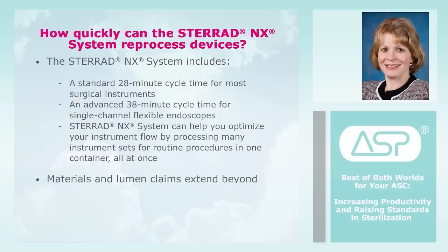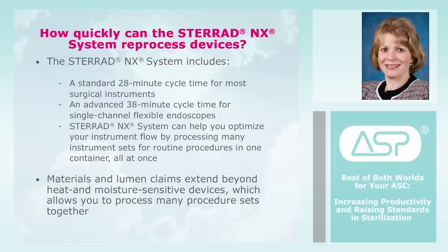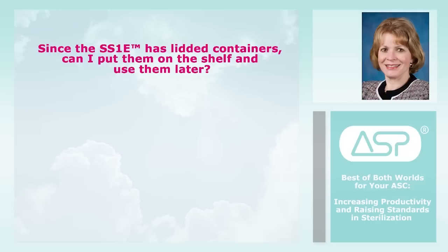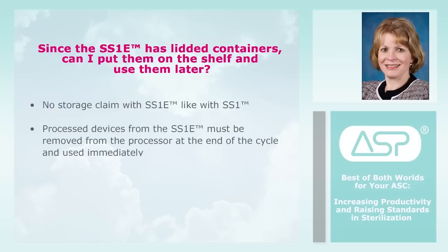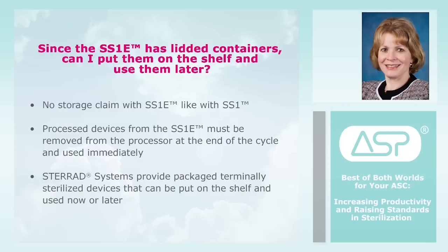As previously noted, the materials and lumen claims of STERRAD systems extend beyond heat and moisture sensitive devices, which allows you to process many procedure sets together. Since the SS1E has lidded containers, can I put them on the shelf and use them later? There is no storage claim with the SS1E, just as there is no storage claim with the SS1. Processed devices from the SS1E must be removed from the processor at the end of the cycle and used immediately. STERRAD systems provide packaged, terminally sterilized devices that can be put on the shelf and used now or later.